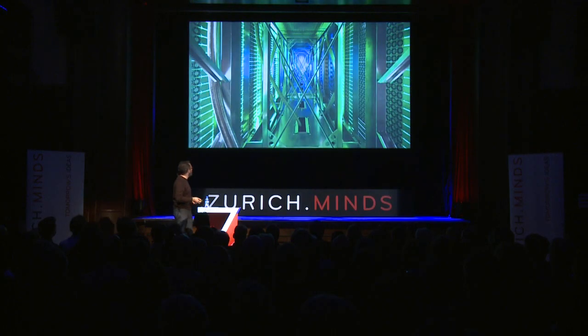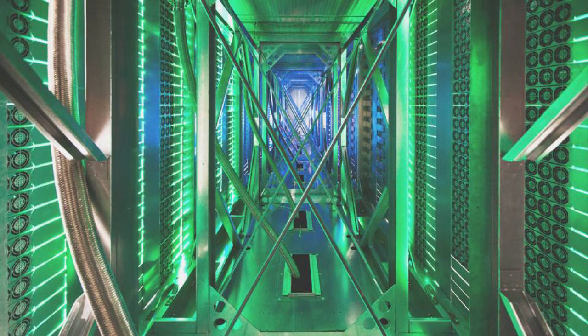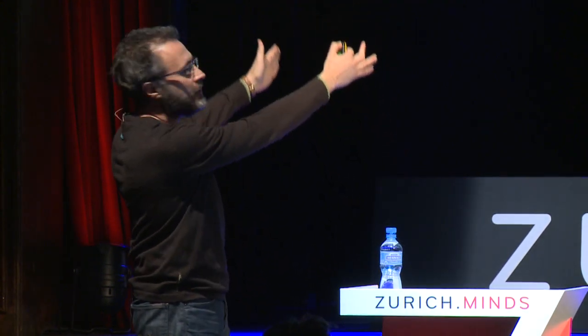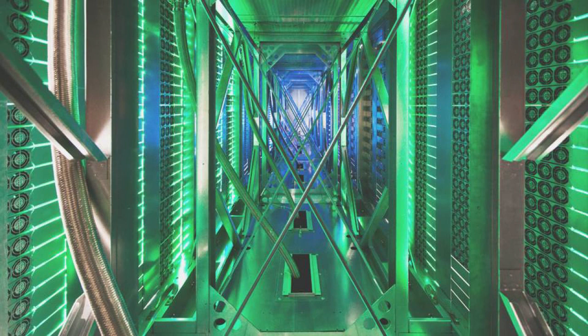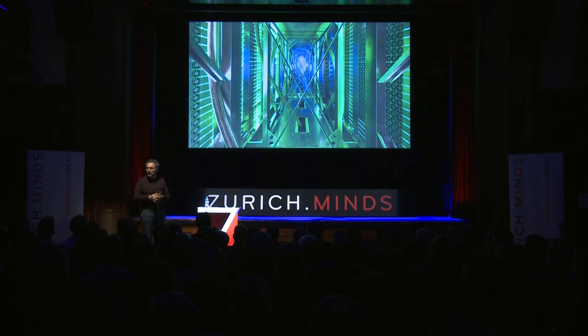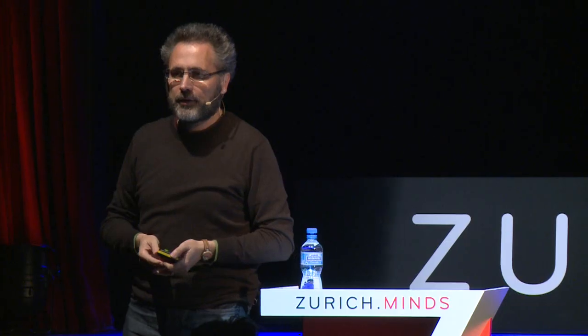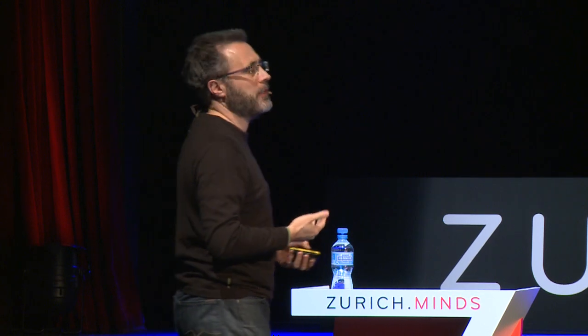And then finally, here's what actually happens on the floor. So this is a view between servers. What you see on both sides are the fans on the back of servers. So imagine air flows through these servers, gets warmed up, because that's where the electronics are, and the hot air goes into this plenum, into this space. And you can see in the foreground a hose. That's a water hose. And the air gets pushed up. Can't see it in this picture, but at the roof of this little mini building, there are coils. And the air gets pushed through those coils. The cold water flows through those coils, and therefore the air cools down, and the whole circle starts again. Very, very simple system and very effective system.